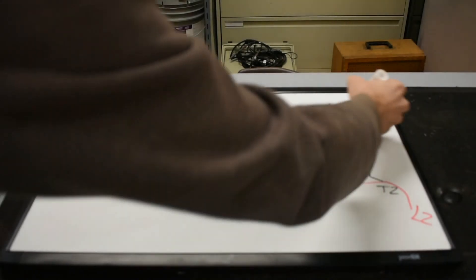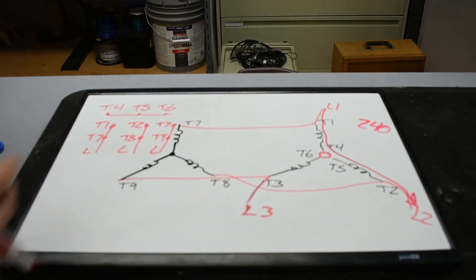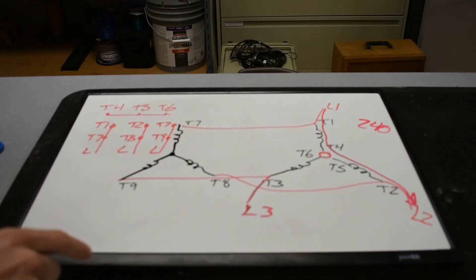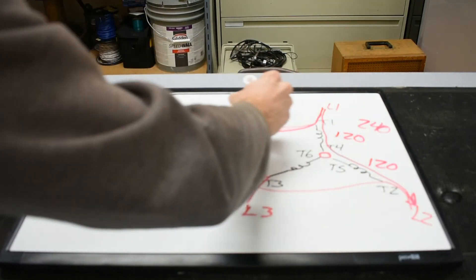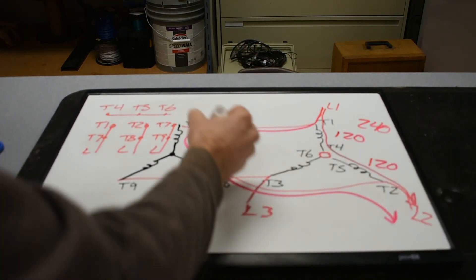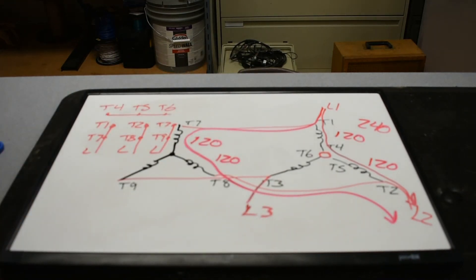Now if this is low voltage, let's say 240 volts, it could be 208 to 240 depending on the input voltage system. But if it's 240, we can see that from here we have two resistors, two coils in series to get from L1 to L2. According to the voltage divider rule, if they're equal resistors, they'll get equal voltage and that'll be 120. Now there's also a second path it will take. So those ones will also get 120. Therefore, at any time with 240, there are four coils getting 120 volts. That was exactly the same with the 480 setup. So the amount of power generated by each one of the coils is the same as it was before. The downside of using 240 volts is that with two paths of current and both of those paths having less resistance than the one path before, we're going to consume a lot more current.